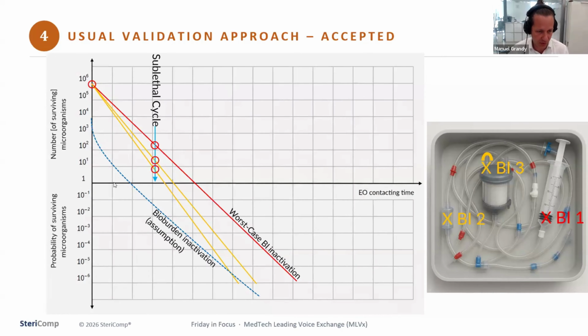So you still have some, this is like, let's say 1.5 hours, for example, or 15 minutes better. So you would do this sublethal cycle and you would measure how many survivors do I have on this BI, on this BI, on this BI. And you would see that I had the highest number of survivors on this BI in the syringe. And this is now your worst case BI inactivation. So this is the most difficult part for the EO to reach, or maybe in other words, to create lethal conditions is this BI. And this you want to know. This is now your worst case BI inactivation, your rate. And we'll come to how you're going to use this.